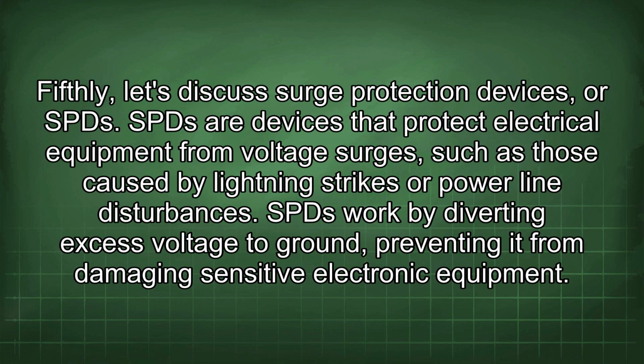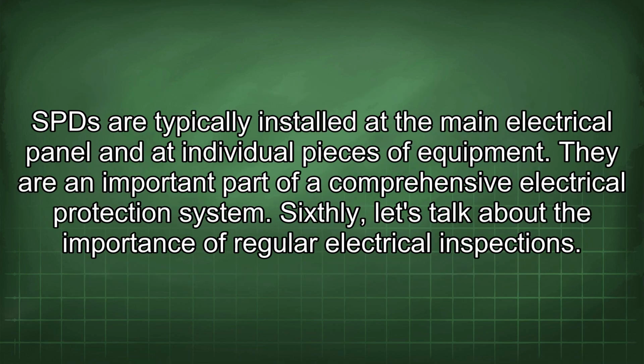Fifthly, let's discuss surge protection devices, or SPDs. SPDs are devices that protect electrical equipment from voltage surges, such as those caused by lightning strikes or power line disturbances. SPDs work by diverting excess voltage to ground, preventing it from damaging sensitive electronic equipment. SPDs are typically installed at the main electrical panel and at individual pieces of equipment. They are an important part of a comprehensive electrical protection system.